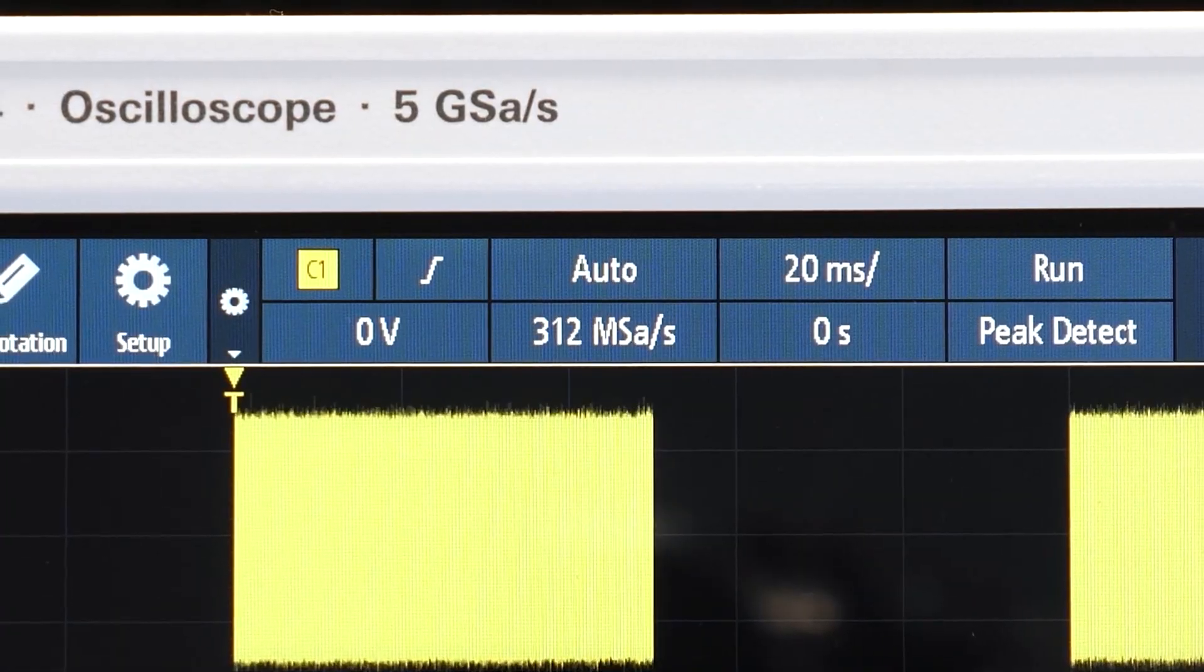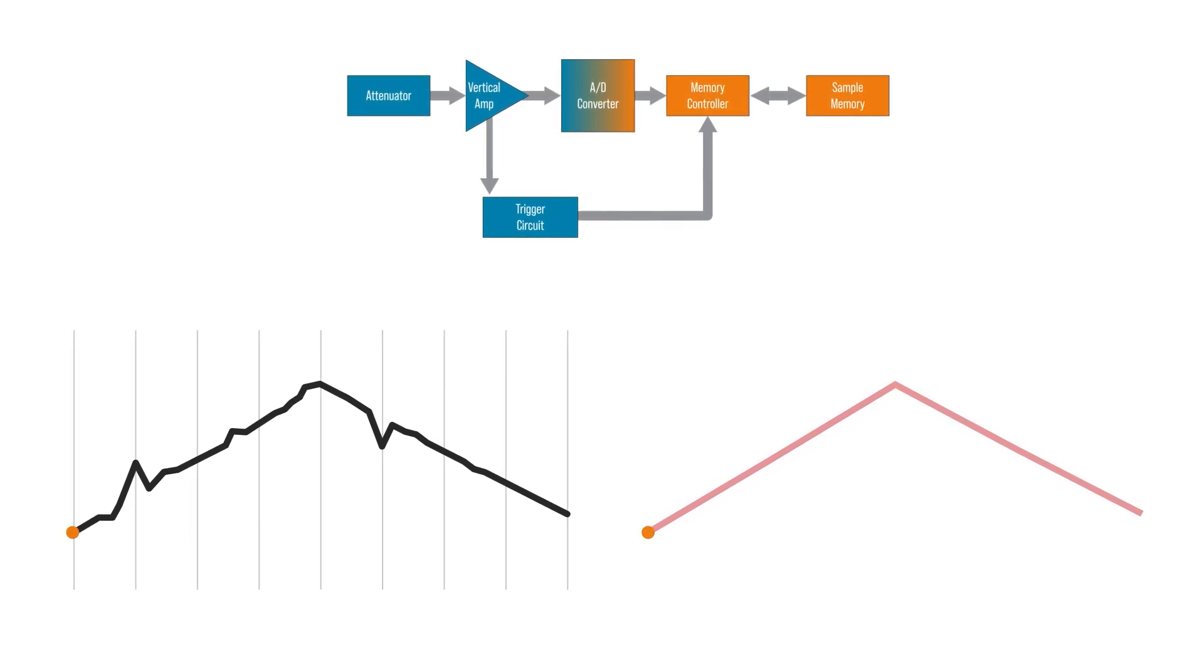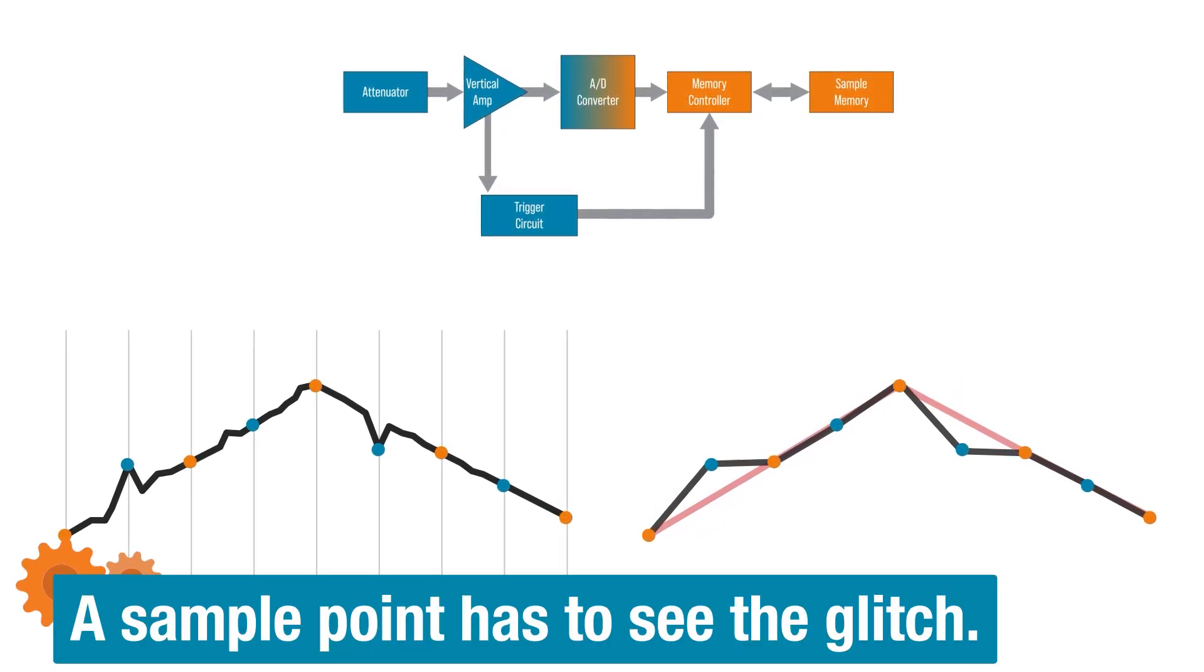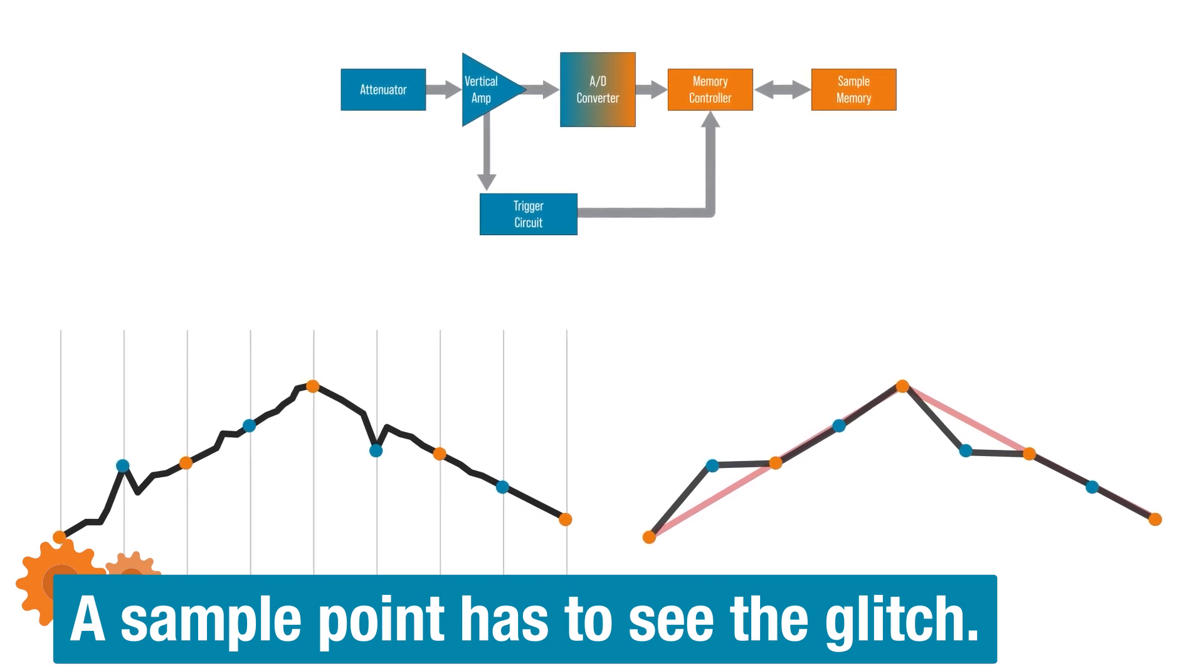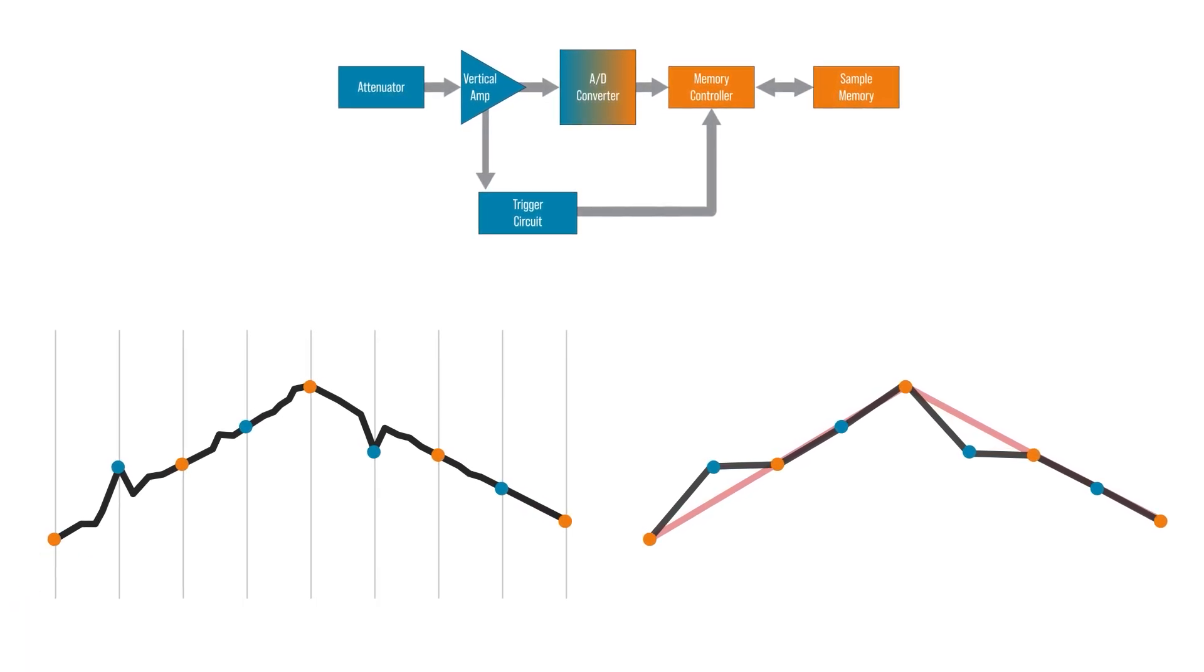In other words, the scope might say 312 mega samples per second, but the ADC is still running at its max rate. Now instead of throwing away those samples, peak detect mode checks for a max and min value. That way if there is a glitch or peak between the waveform samples, then we can still see them on the scope.